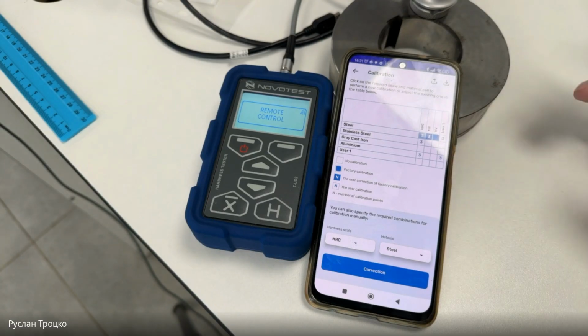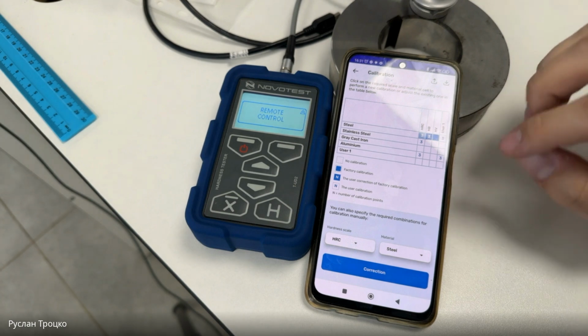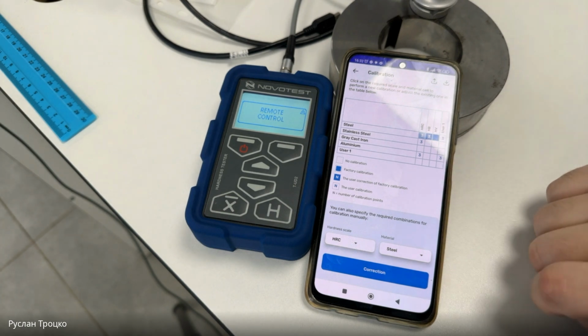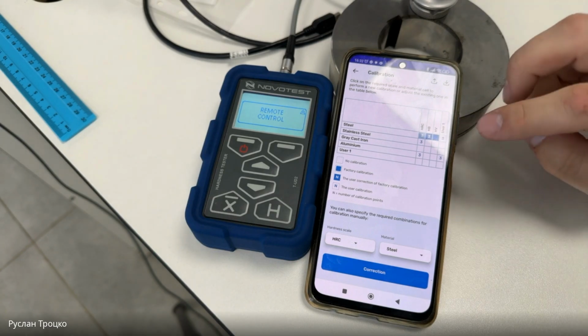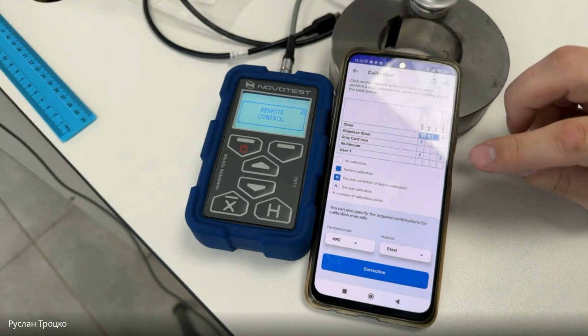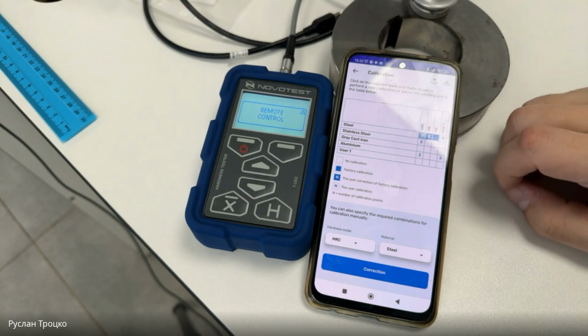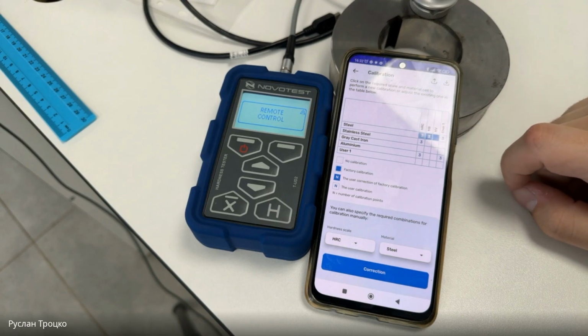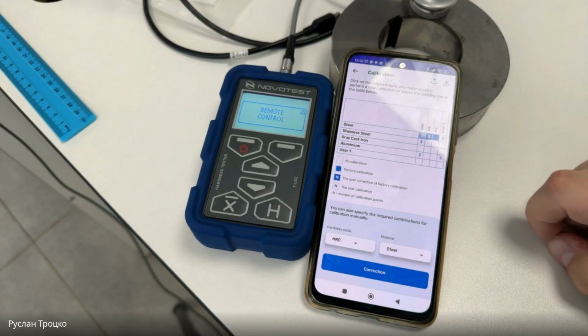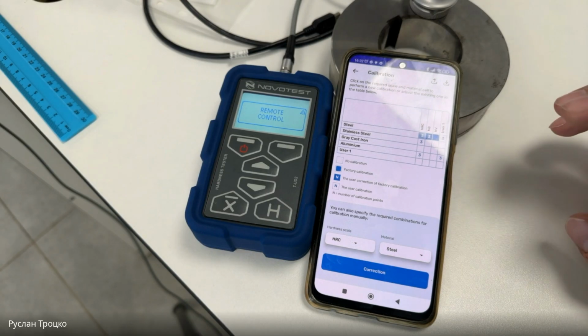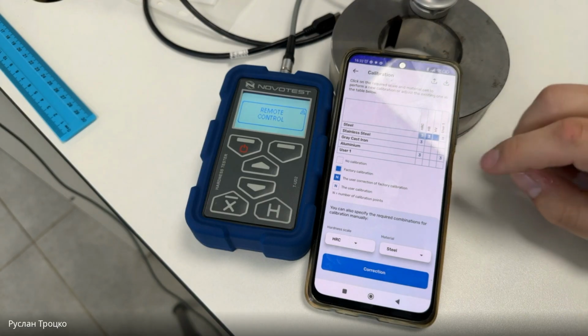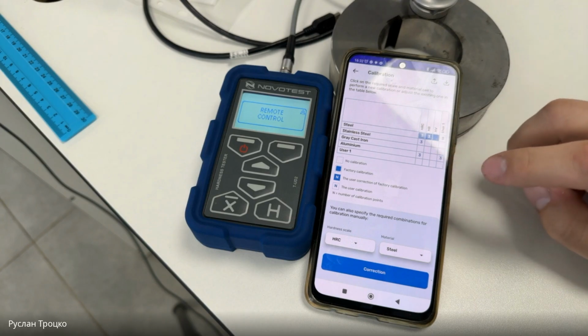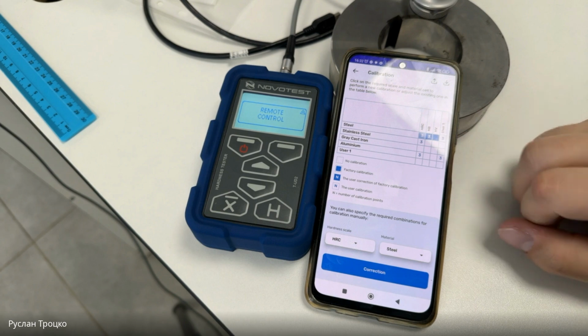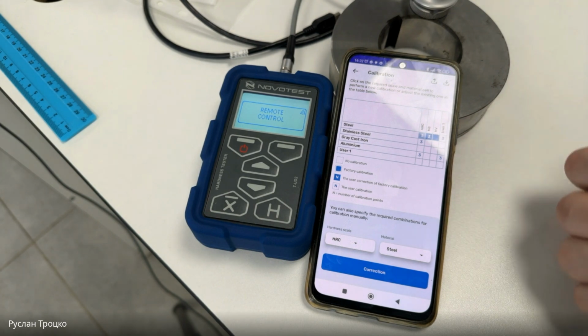White cells, there is no calibration. Blue cells mean this is a factory calibration. A blue cell with a number on it means there was a user correction. You can actually correct the factory calibration. You can do a small adjustment. And if you see a number, for example, number 3 on a white cell, it means you did this calibration by yourself. It's your own calibration.